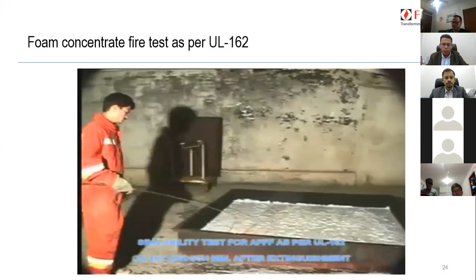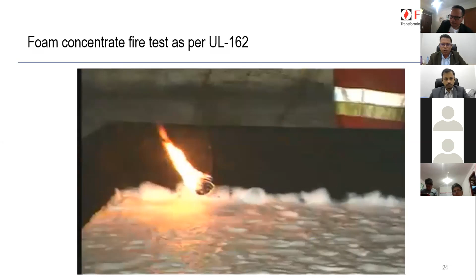And this is a sealing test to ensure that the foam has properly sealed the edges of the fire test pan. So a torch is moved along the edge of the pan to see if any of the edges are open. In case there is a fire at the edge, then the foam fails the test.